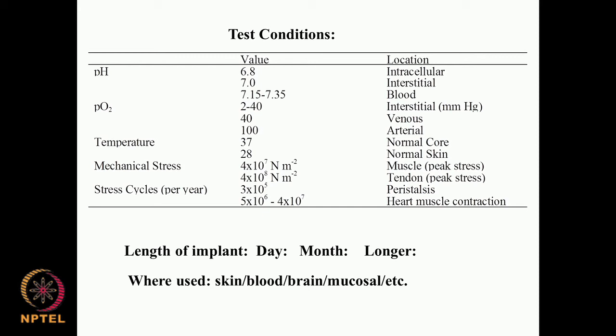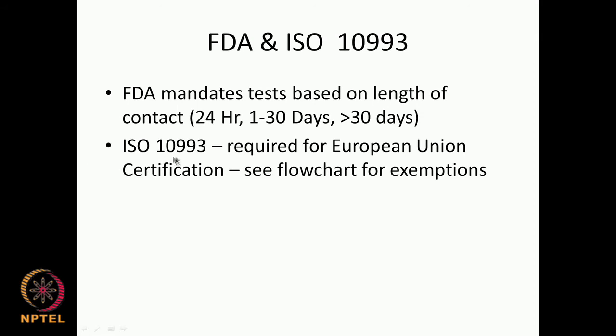The test conditions vary quite a lot. The locations where the biomaterial has to be implanted and the duration both vary considerably. FDA mandates tests based on length of contact: 24 hours, 1 to 30 days, or greater than 30 days. ISO 10993 is the European Union certification. One needs to consider both FDA and ISO guidelines for testing of biomaterials.